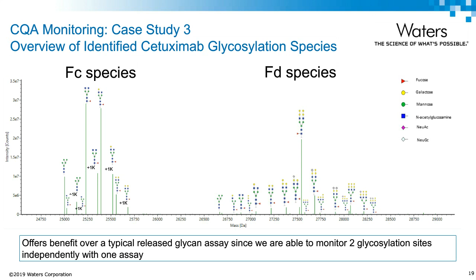Let's take a deeper look at some of the relative percentages of each of these. Here we see the Fc glycosylation on the left side and the Fd on the right side. This was a triplicate injection experiment, and as you can see, or maybe not, the error bars for this analysis are almost non-existent, meaning we really have very reproducible results across this analysis. Percent RSD for each of these is going to be less than 3%. And as you can see, even some of those low-level species still have great reproducibility. This is just one example where a subunit-based analysis gives us a distinct advantage over the standard released glycan assay, and we can do this quickly, easily, and reproducibly with BioAccord.